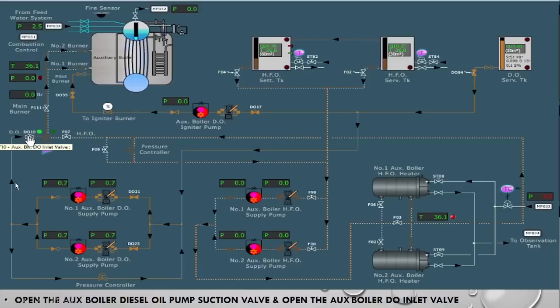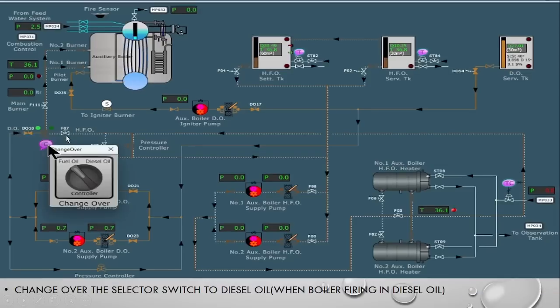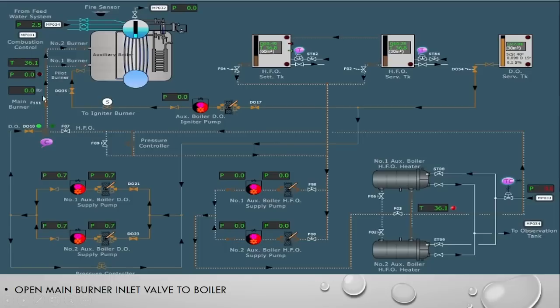So till now we have opened the valve for the igniter pump line, the suction and discharge valves, and DO10 to ensure all lines in the DO supply pump are open. This is the changeover arrangement — if you open this side, DO will come; if you open the other valve, heavy fuel oil will come. We now put the changeover valve to diesel oil so that the temperature controller gets deactivated, because diesel oil does not need heating — it is well-heated at room temperature of around 30 to 40 degrees Celsius.